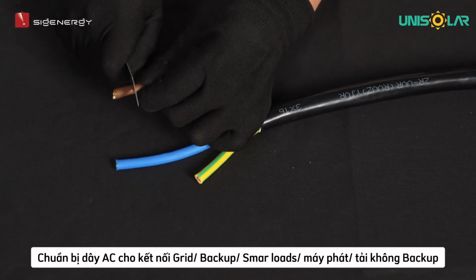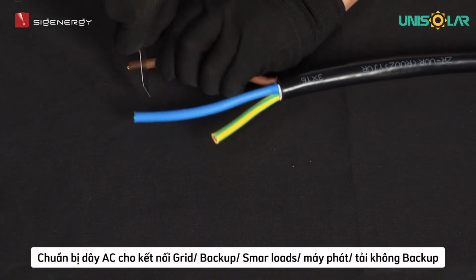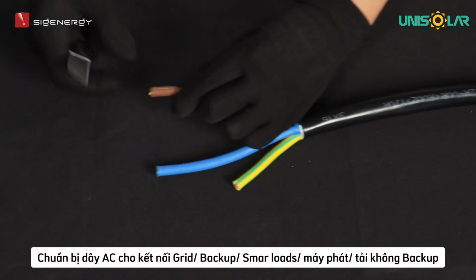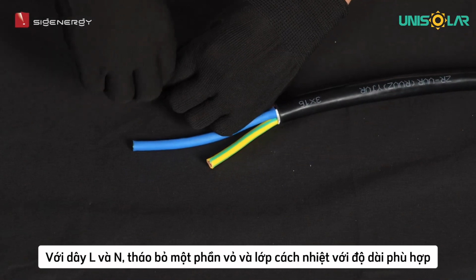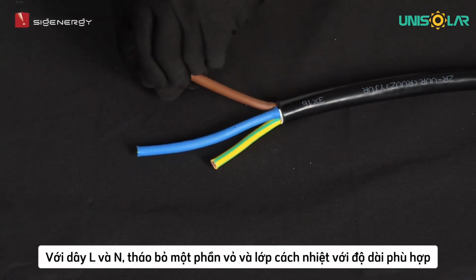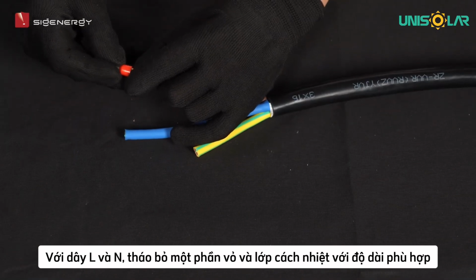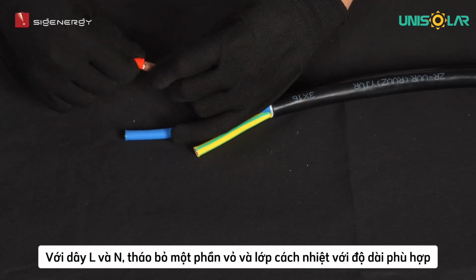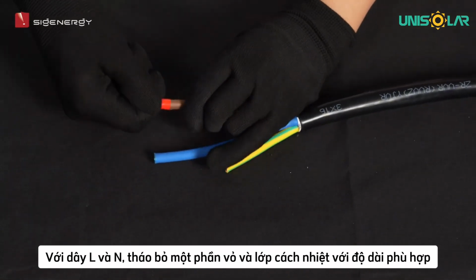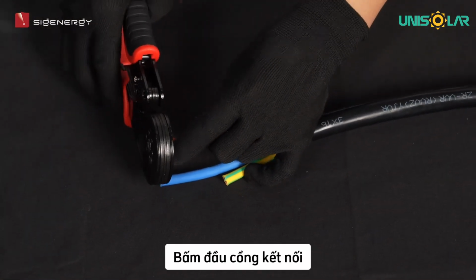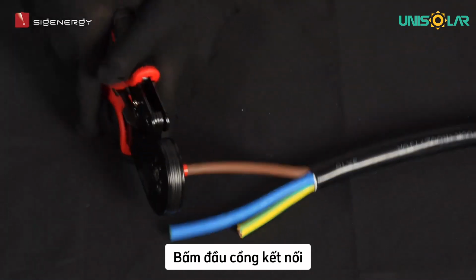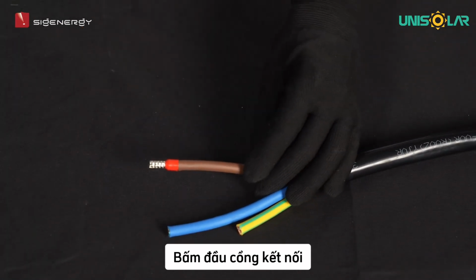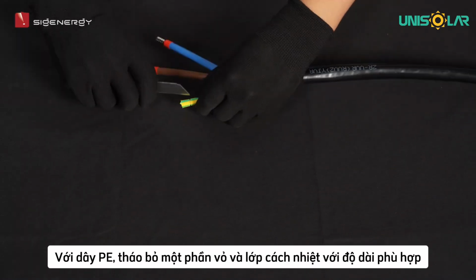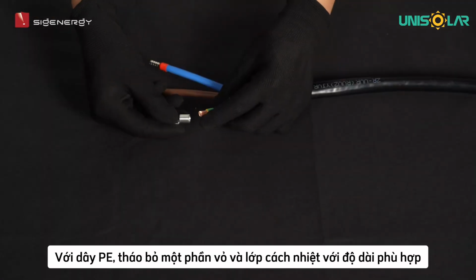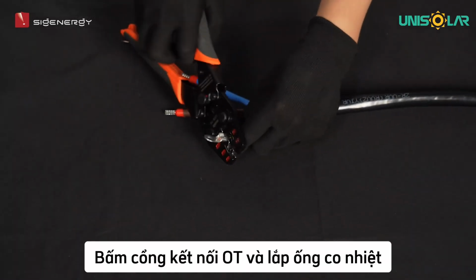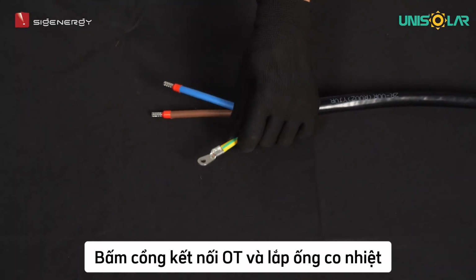Prepare the AC cable for grid, backup, smart loads, generator, inverter, non-backup connection. For L and N line, remove an appropriate length of the jacket and insulation layer from the wires. Crimp tube terminals. For PE line, remove an appropriate length of the jacket and insulation layer from the wires. Crimp OT terminals and install heat shrink tubing.